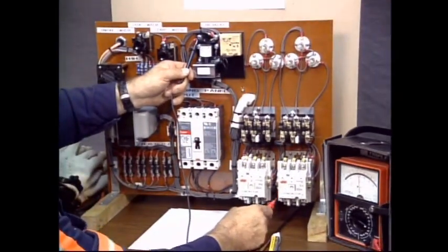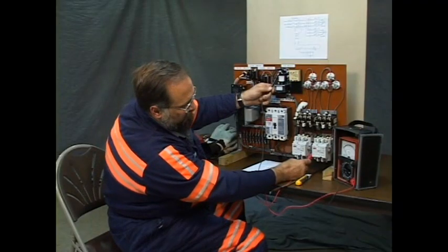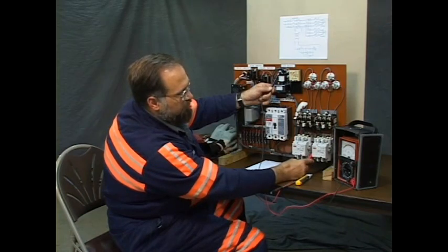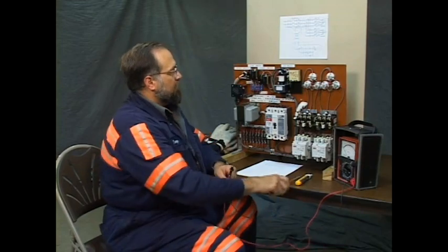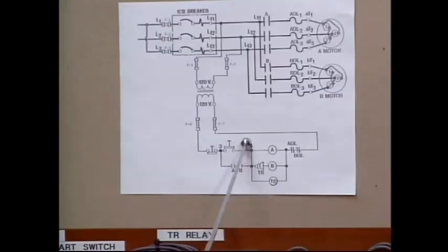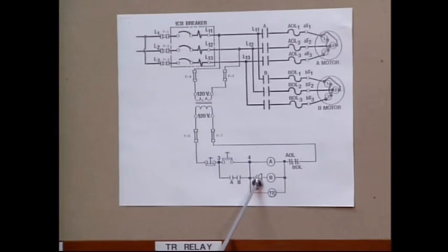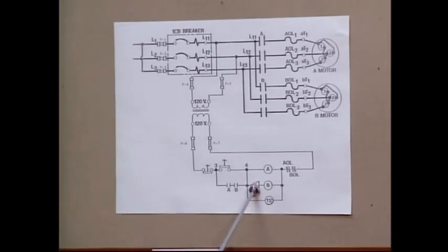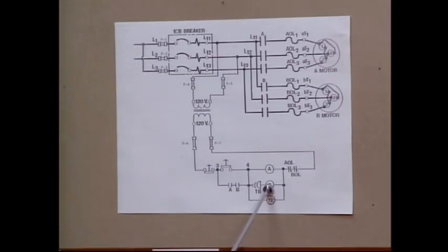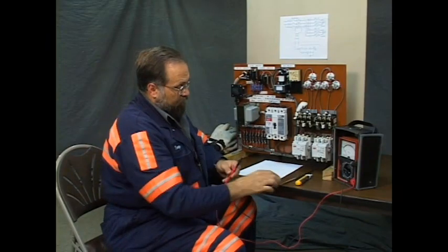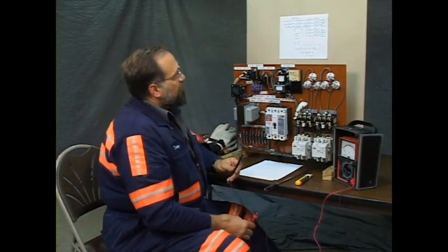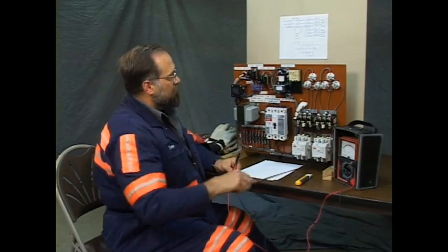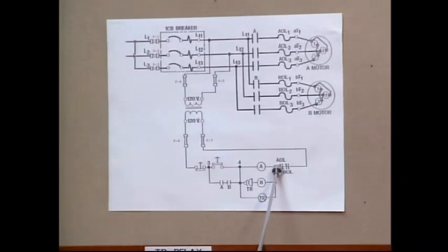Look at that. I have a full scale needle deflection. It shows 0 ohms resistance. That wire's great. It's a good connection. Well, so far we've checked from power to the mercury tube to the coil. We've checked from the mercury tube to the B coil. Let's check from the B coil to its return. You know, power to the circuit's only half of it. You have to have power away as well. So I'm going to check from the B coil. The first point on its return path would be BOL.